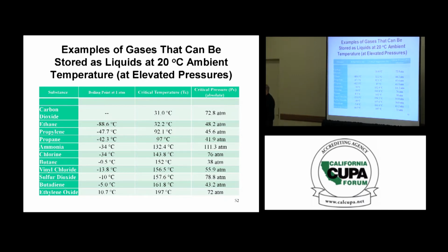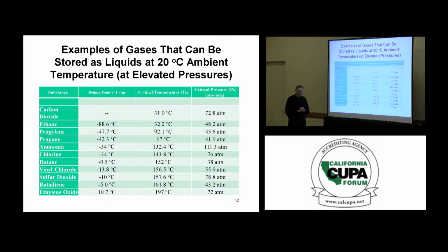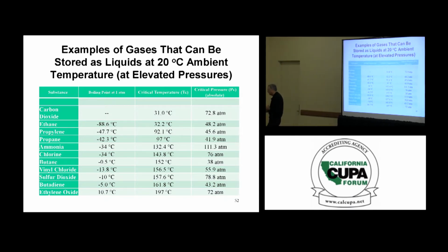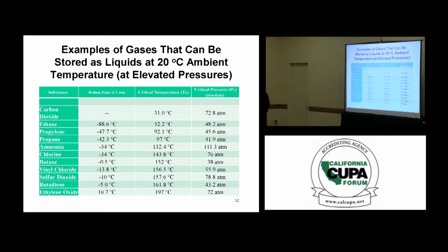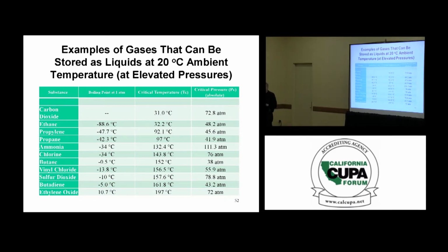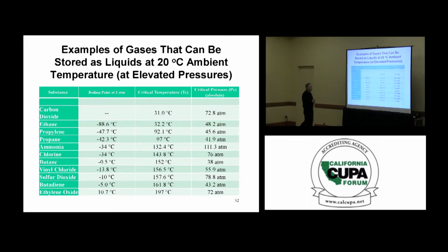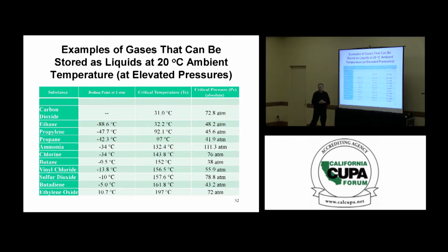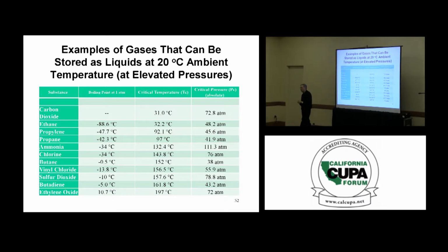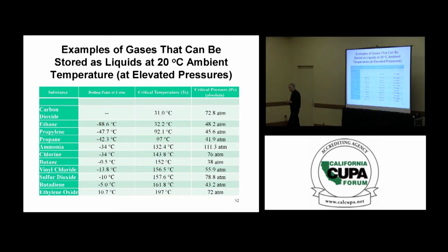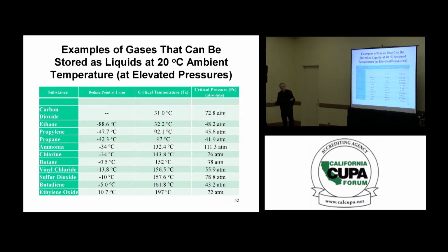So I've got a carbon dioxide container in one of my facilities I inspect as a CUPA inspector. And this one happens to be a normal atmospheric temperature situation where I'm not storing at low temperature, so I've got it in a room that is at 20 degrees centigrade. So, do I have liquid CO2 in that container?